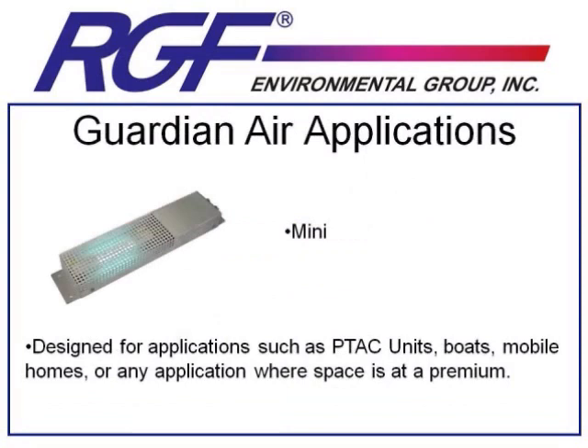In case you've got an air system like a PTAC unit or a boat or mobile home air conditioner that doesn't necessarily have the 5 to 9 inches of duct clearance for one of the PHI models, we've developed the Guardian Air Mini. The Mini mounts flush inside of a PTAC or other system, and as long as air passes over the top of it and the UV light isn't visible, it can be a great product for any of those tight-fit applications. The size limitation is really one room no bigger than 1,000 square feet. We've successfully installed them in hotel PTAC units, in boats, in mobile homes, or in any application where space is at a premium.